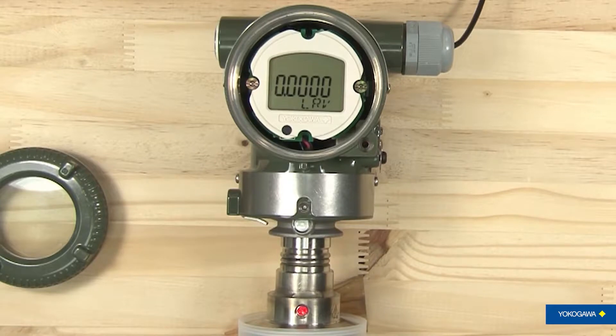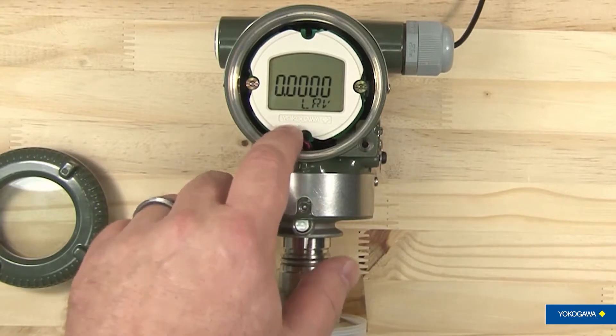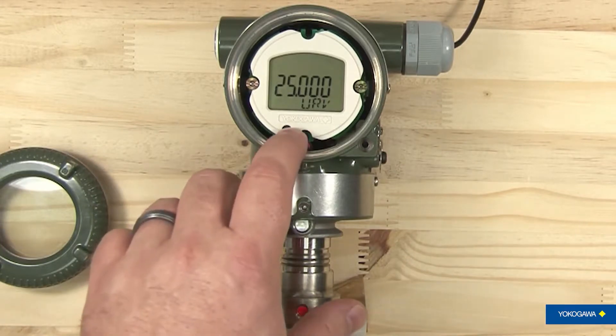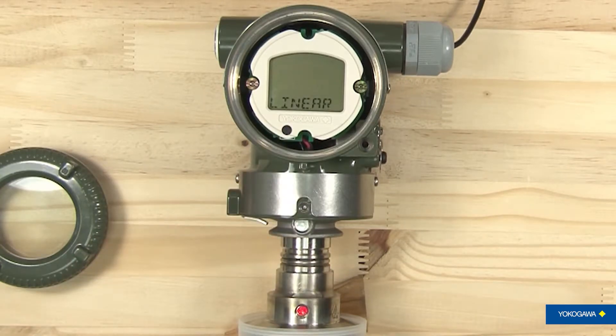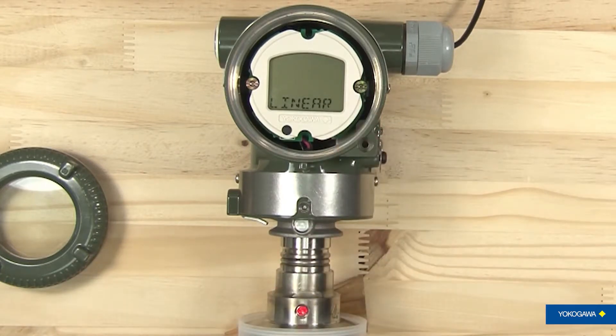Press it again and it comes to unit of measure — in this case it's set to PSI, so it tells you the unit and PSI. It will continue to alternate between the item you're on and how it is set so you'll have an understanding of what it is. Hit the next one and you're looking at your low range value, which is what your four milliamp is set on — it's set to zero on this one. Your upper range value, which is what your 20 milliamp is set to, is set for 25 PSI. Go to the next one and you're looking at your damping, which is how quickly the transmitter transmits the pressure that it's reading. You've also got how the signal is transmitted out, whether it's linear or square root — in this case you can see on the screen that it is set to linear.